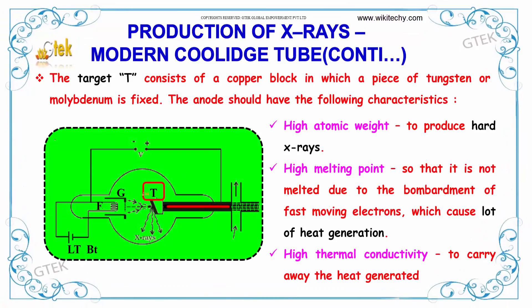The target T consists of a copper block in which a piece of tungsten or molybdenum is fixed. The anode has the following characteristics: it has a high atomic weight to produce hard X-rays, a high melting point so it is not melted by the bombardment of fast-moving electrons, and high thermal conductivity to carry away the heat generated.